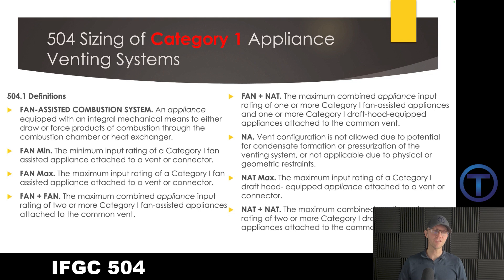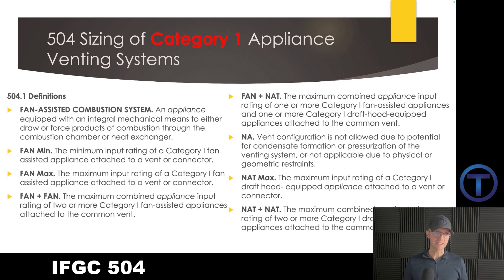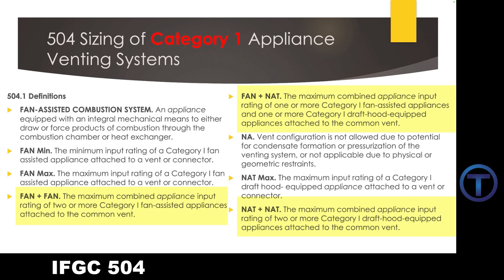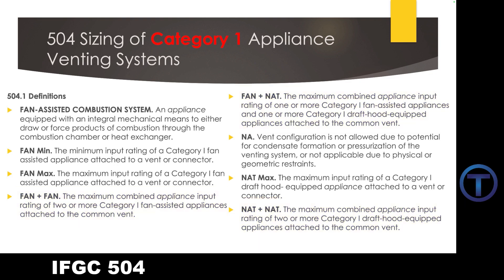Fan assisted combustion system, fan minimums, fan maximums. As we get into the sizing table, we're going to see these combinations. Please notice that the definitions which have a plus sign are for multiple appliances. So if it's fan plus fan, then we have two or more Category 1 appliances that have a fan to assist the vent. If it's fan plus nat, that means one has a fan and the other is natural draft. If it's nat plus nat, then we have natural draft and another one or more Category 1 appliance. That's what these definitions with the plus sign are all about.